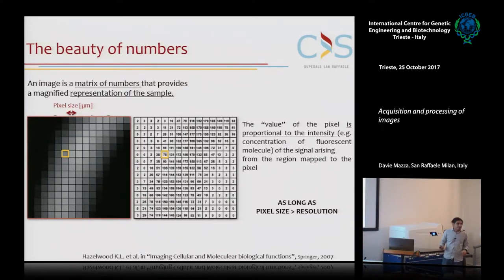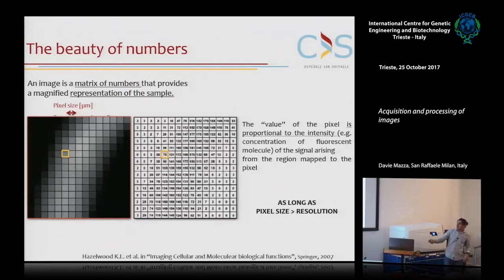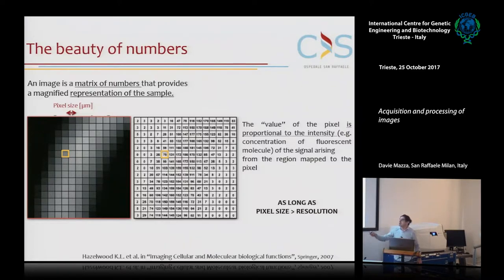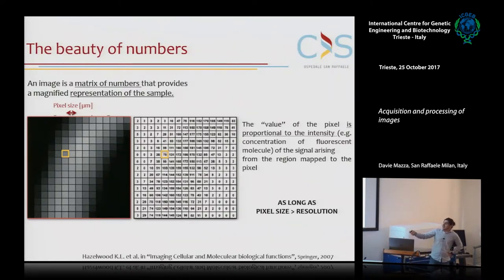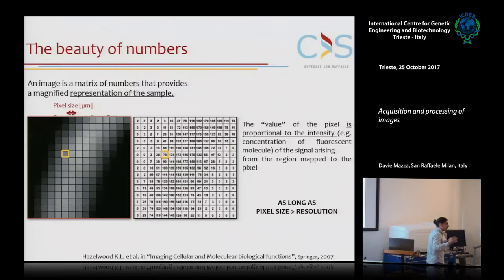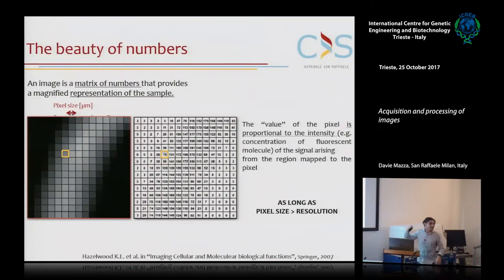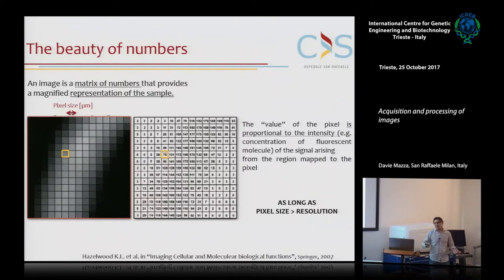Basically, an image in modern microscopy is a matrix of numbers. We have a matrix with many little boxes; in each box you put a number, which is the intensity of the area of space in the real sample that maps to that particular pixel. The size of the area mapped into that pixel is the pixel size, typically expressed in microns. During the practicals, we'll do a small exercise to compute this pixel size given the parameters of your instrument, like the magnification of your objective.